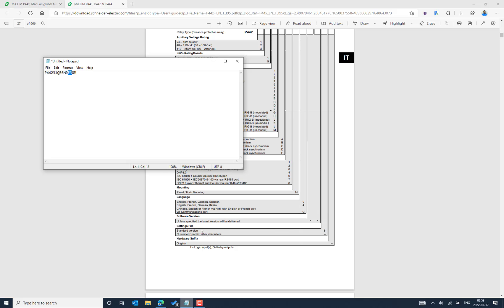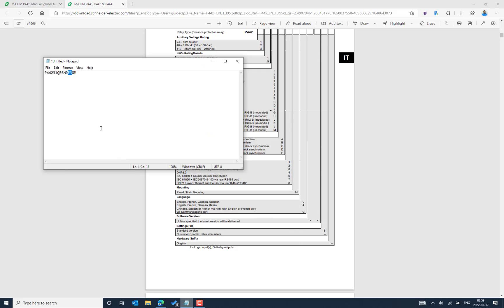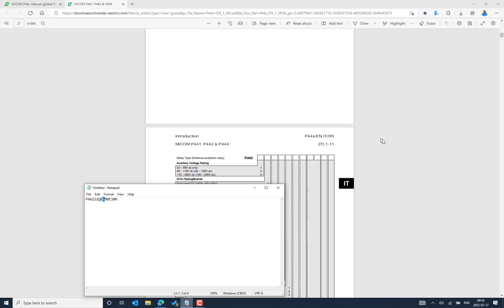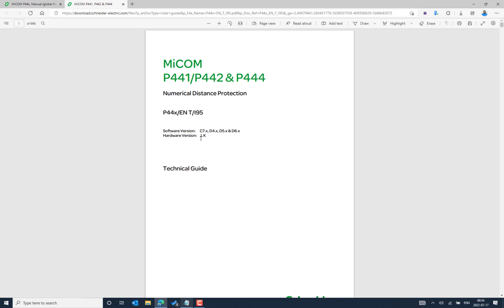The standard version has maximum benefits, but if the customer specifically orders a different application, this will be customized during the firmware programming of the P40 series Micom IEDs using the proprietary programming tool. The last digit is the hardware suffix, and most importantly the communication module — for example, 6 stands for IEC 61850 communication — along with further inputs and outputs. It's important to understand the latest manual reference.